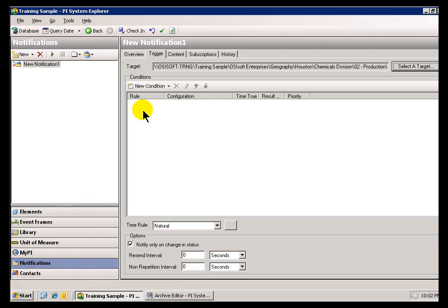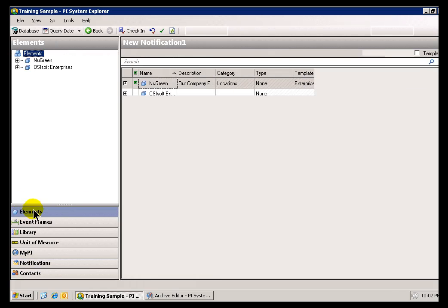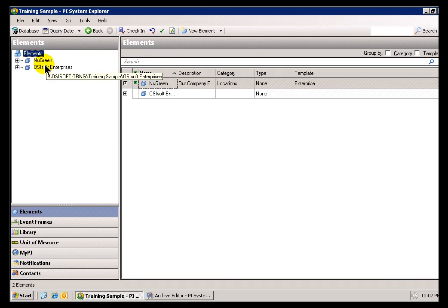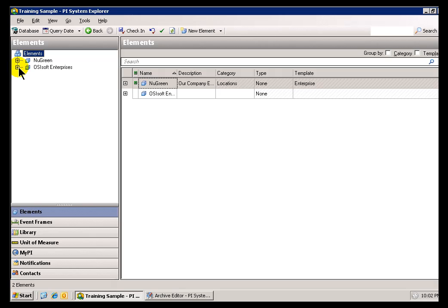Now, one of the things that people have said is, well, hold on a second, does that mean if I want to do a Notification, just a simple Notification on a PI Tag, I have to create an Element Structure that contains that PI Tag? Well, yes, that is true. The Elements are the basis for how we navigate to those PI Tags, those Data References that we're going to do a Notification on.